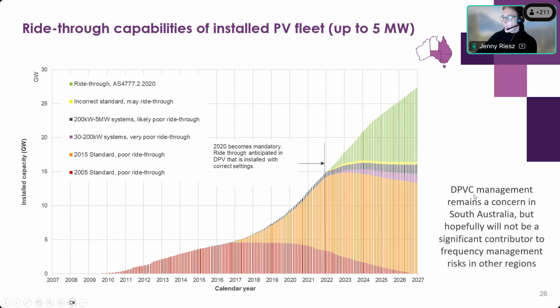Distributed PV contingencies remain a concern in South Australia, particularly if we're operating that grid as an island. As I mentioned earlier, particularly with the low inertia in the island, frequency management with these sorts of contingencies can be quite a significant challenge to manage. But we're very much hoping that we've nipped this in the bud just in the nick of time, so that frequency management and these contingencies will not become a significant problem in the rest of the grid. They'll remain smaller than the largest credible contingency that we're managing from other sources. So yeah, really positive outcome for the industry.